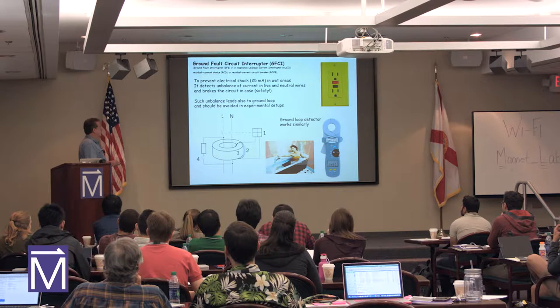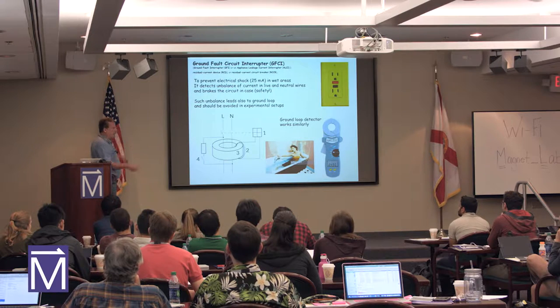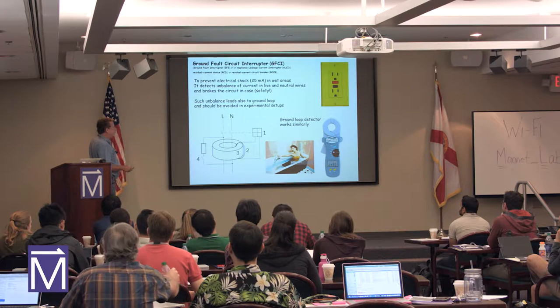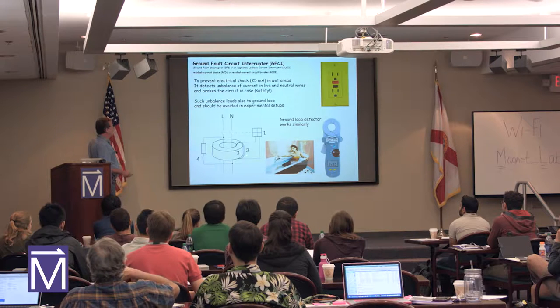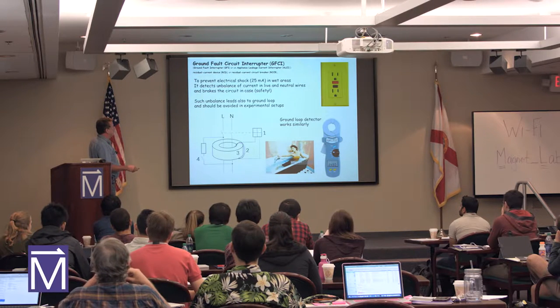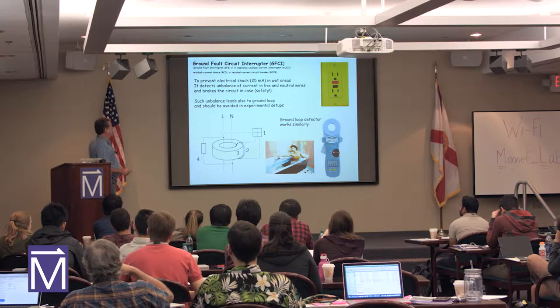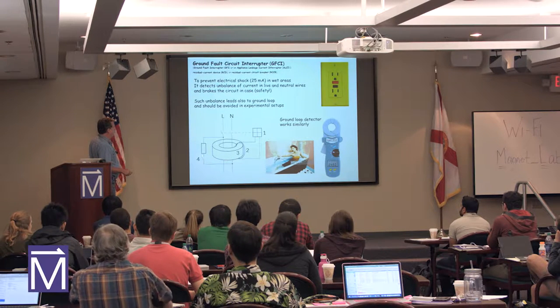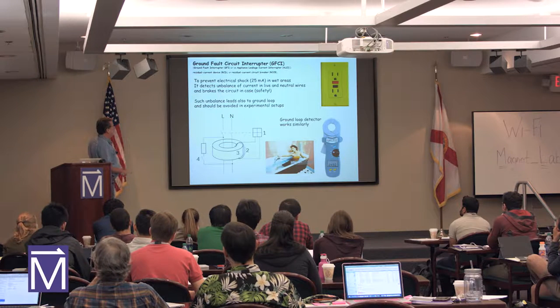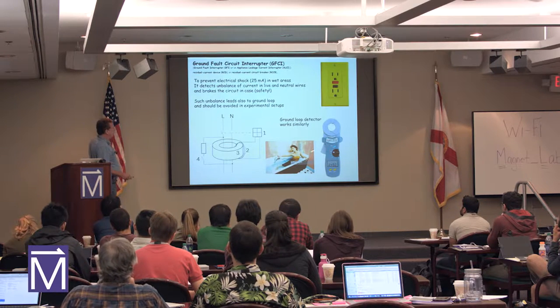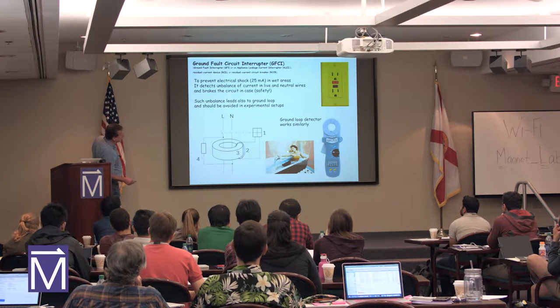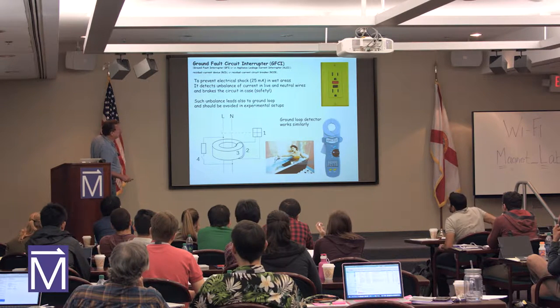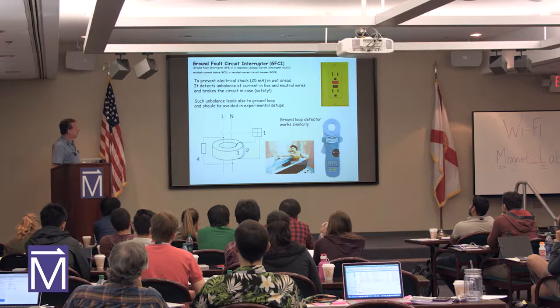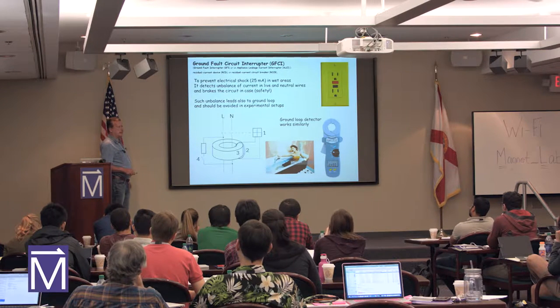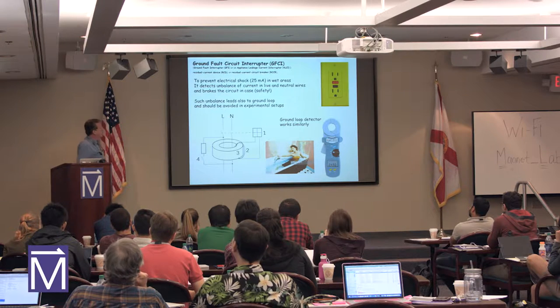When current comes through neutral and leaves through live, when there is balance here, nothing leaks. There is no current in this circuit. When there is imbalance here, this circuit switches off the current in this outlet to prevent situations like this, where this lady uses a hair dryer in the bathtub. Actually, now hair dryers usually have this device installed.